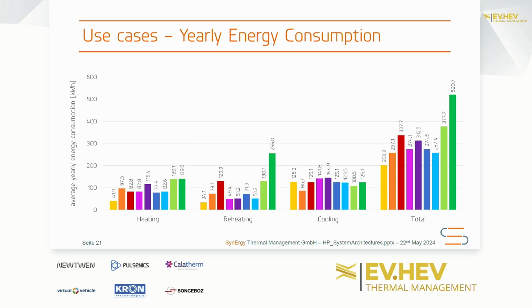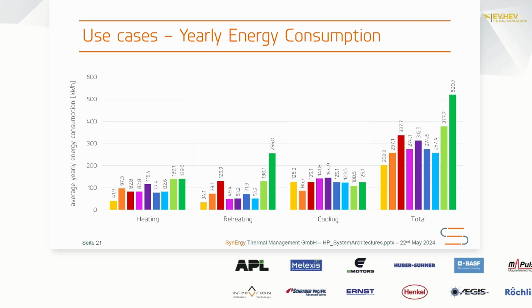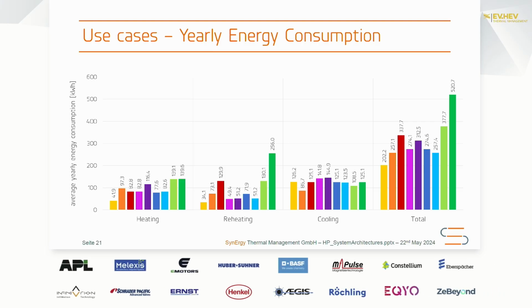So on the left side, on the heating cases, the yellow bar, that's the CO2 system shown before. Because we have a higher heating performance, this is using less power from the battery to heat up the cabin and the battery compared to a YF system or a system that does not have a heat pump, which needs to provide this all electrically. But maybe just go back one step.